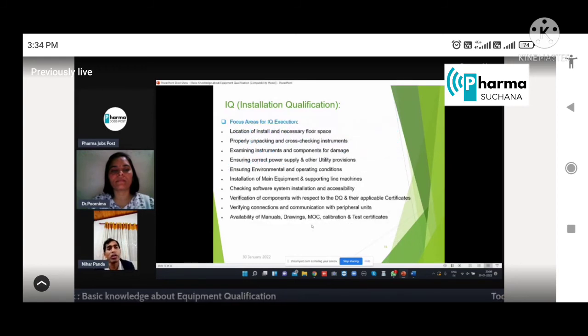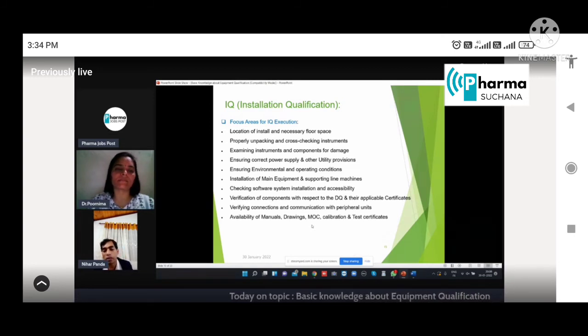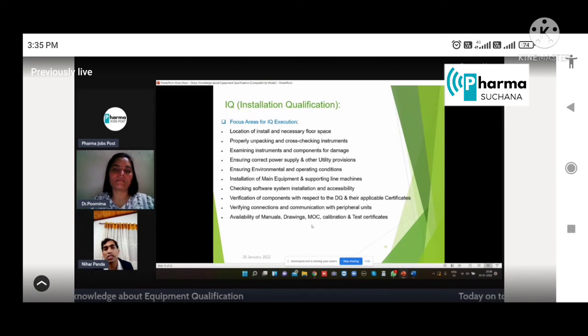Then during IQ, what are the focus points? What should we focus on more and check more? Like location: where the equipment is to be located, where the actual feasibility is, what the orientation of the equipment will be, what the direction of the equipment is, where it will be open, where it will be closed, where it will be accessed. All of that, according to the location feasibility, we have to check. That is the most important.